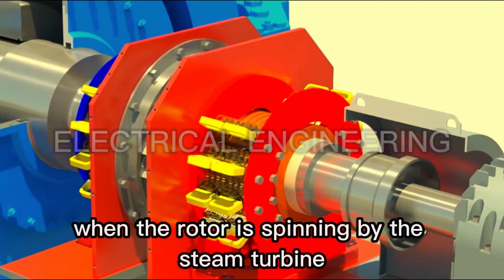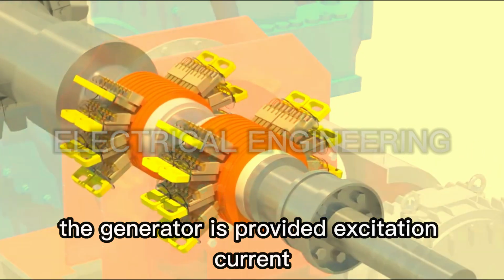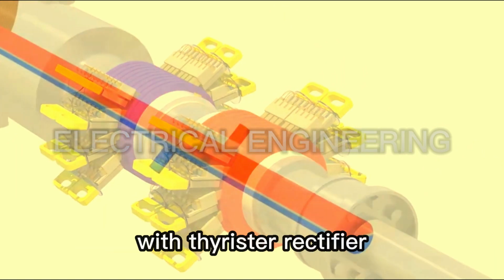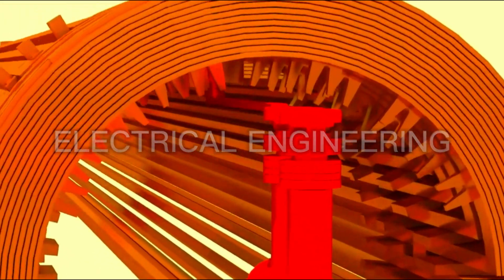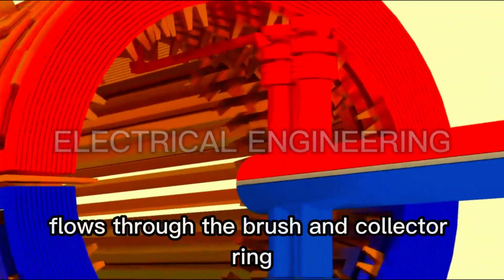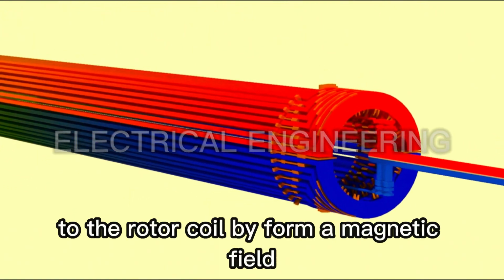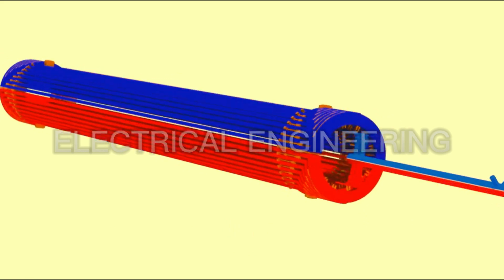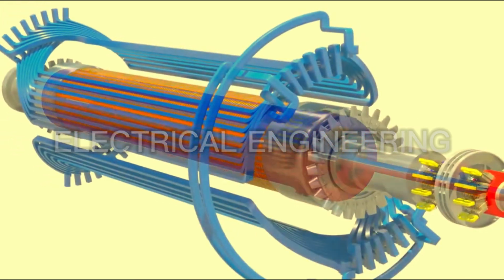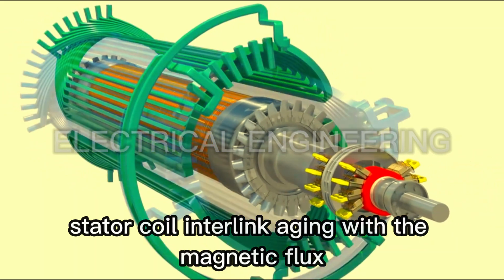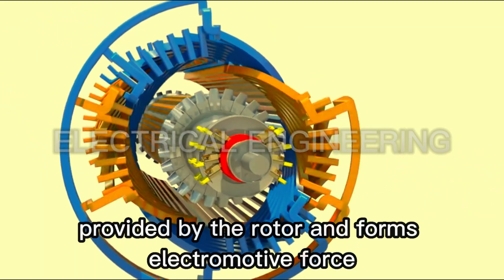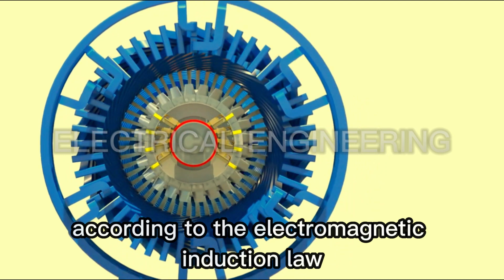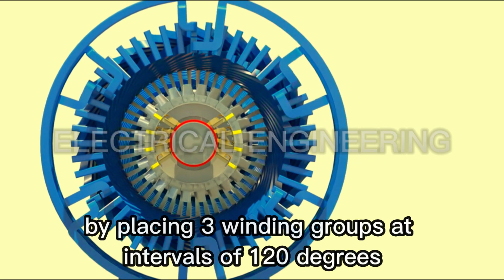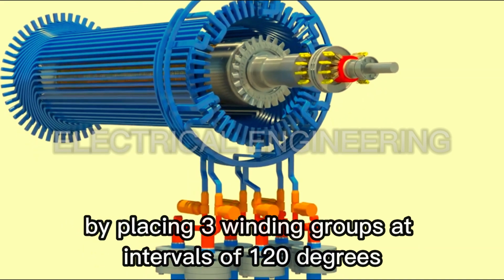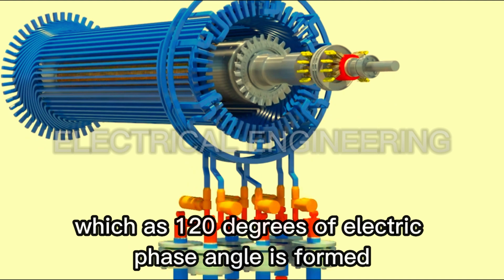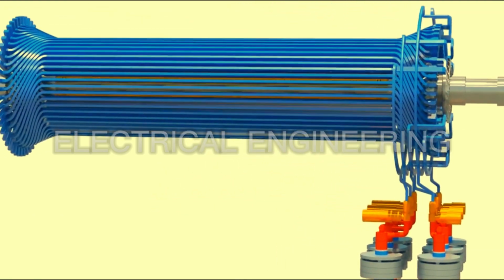When the rotor is spinning by the steam turbine, the generator is provided excitation current from the static excitation system with thyristor rectifier. The current provided from the exciter flows through the brush and collector ring to the rotor coil to form a magnetic field. The stator coil interlinking with the magnetic flux provided by the rotor forms electromotive force according to the electromagnetic induction law. By placing 3 winding groups at intervals of 120 degrees, 3-phase alternating current, which has 120 degrees of electric phase angle, is formed.